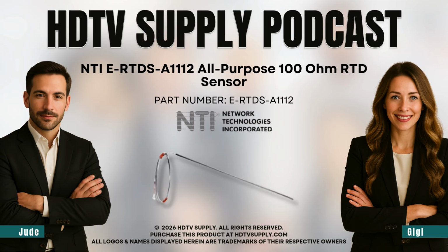Okay, that makes sense. Let's get into the core of how it works. The technical signature, 100 ohm Pt 385. Right. This is the sensor's whole identity. It's a resistance temperature detector. So the P is platinum. What about the other numbers? The 100 ohm is its resistance at exactly 0 degrees Celsius. It's the baseline. And the 385, that's the temperature coefficient. The what? It's basically the standardized curve that defines how much the resistance changes as the temperature goes up. It's the industry handshake. Every controller is programmed to understand that exact curve.